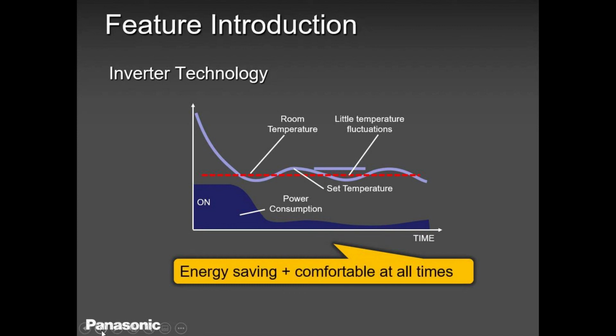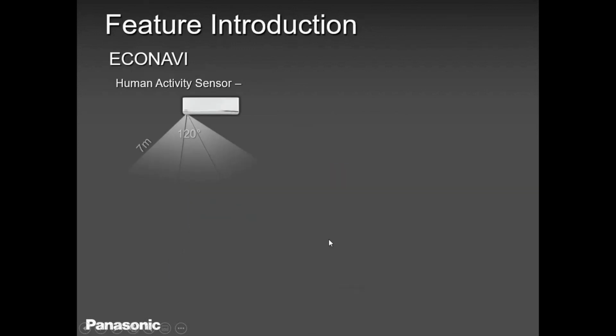Anyway, so I was talking to you about this power board that has the entire one-piece control board at the outdoor unit. So one is the control side, and the other one is the rectifier, AC/DC, and this is your intelligent power module. This is where you'll get all the error codes, F99, F90, F96, depending on the situation. So it could be the outdoor board, or it could be the compressor. So if you are not doing heat pumps on a daily basis, it is important to invest in a phase checker, inverter phase checker. It won't take more than 3 to 5 minutes to find out if the problem is with the compressor or with the outdoor board. Unless you are doing heat pumps on a regular basis, it's very easy. And I will explain to you why it's very easy. Because when the outdoor unit compressor is defective, the fan will come on.